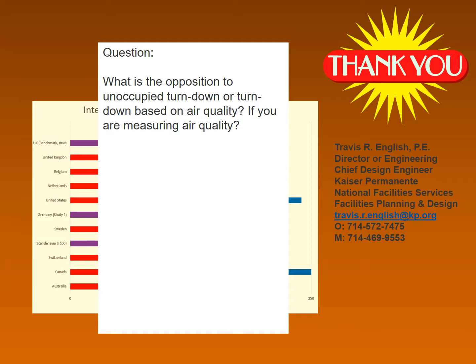That's just been a tough thing to write into the code. At the national standard level, it breaks down into a couple questions. If you have a lighting occupancy sensor in a patient room, then when it shuts off and the room is bona fide unoccupied, you can turn down the systems. Under California code, you can turn down the systems to, I think, 20% is the number. But patient rooms are very frequently not unoccupied - they have somebody in them, that person is just asleep, all the lights are off and the guy's asleep. That's not an unoccupied room.